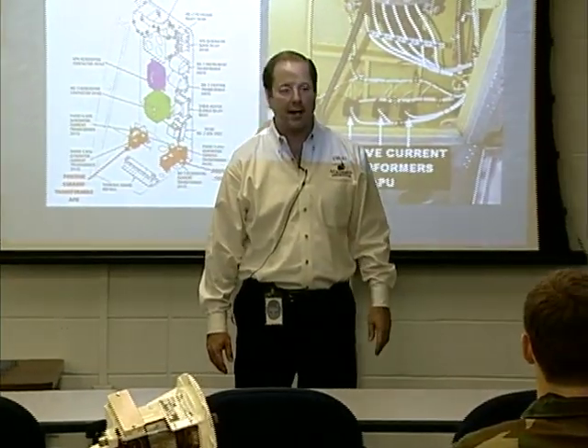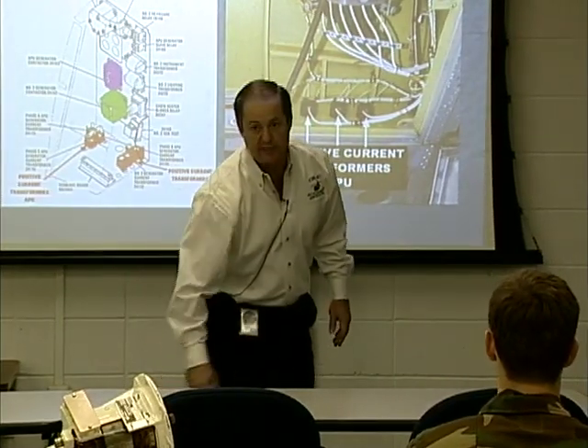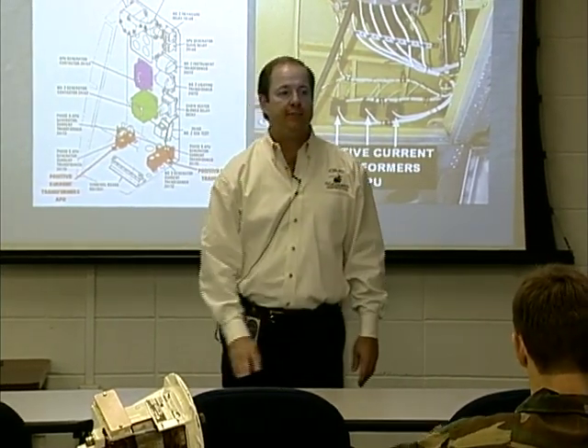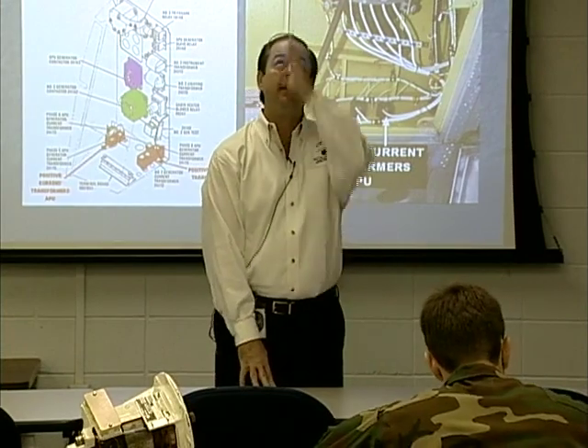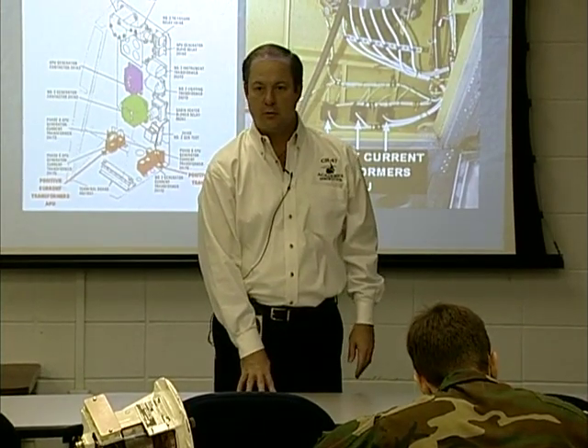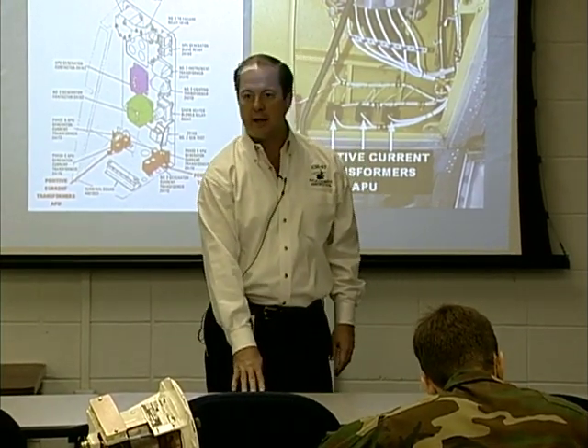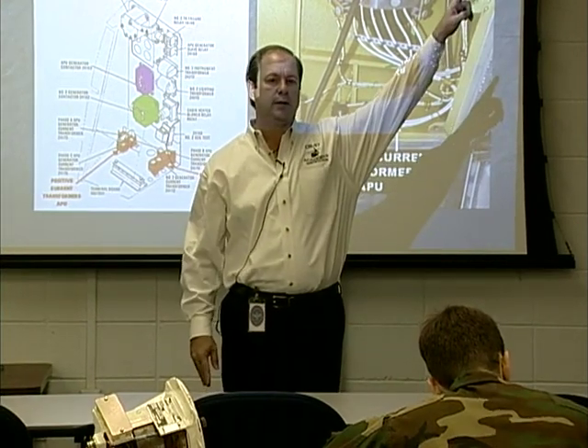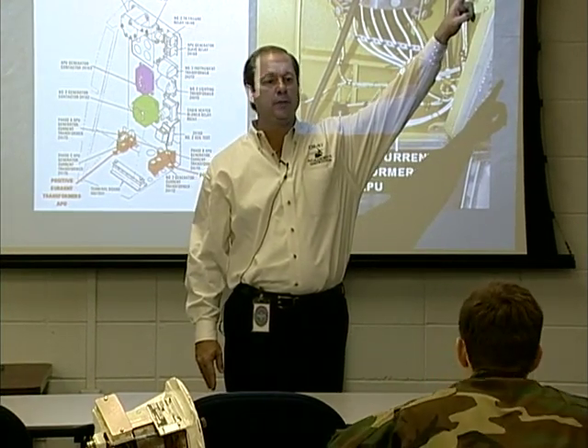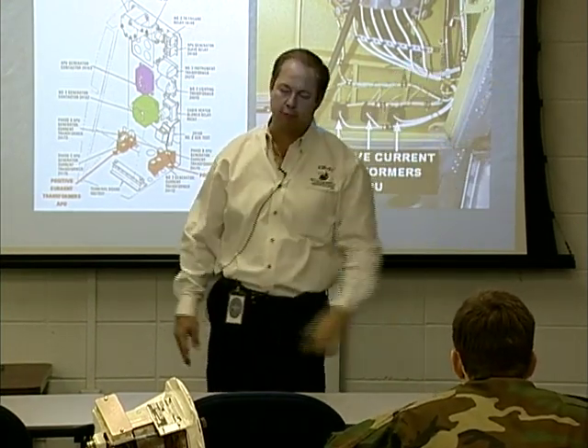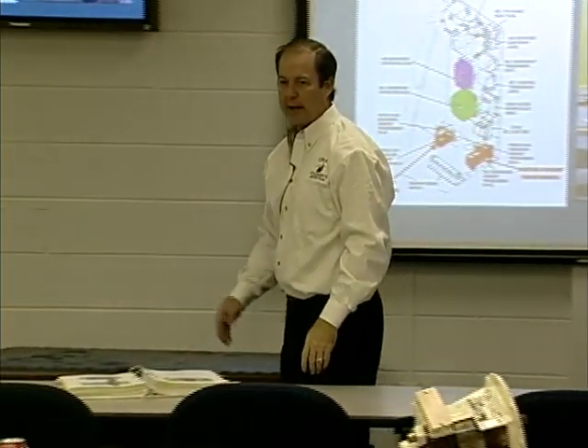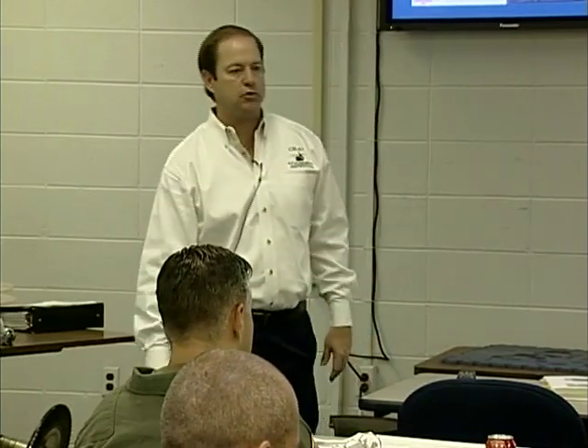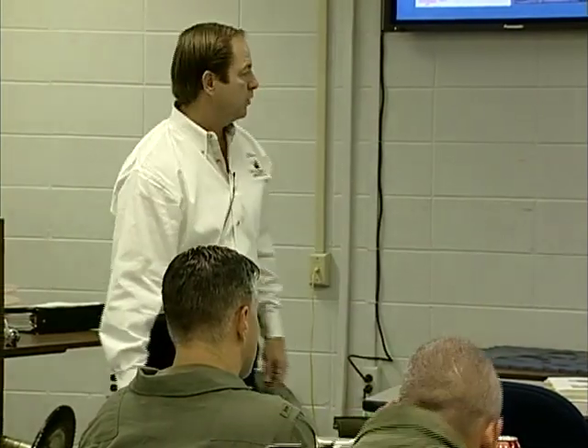Where they are located: if you stand on the tarmac, if this is my ramp down and level, if you butt yourself up against directly underneath the APU, against the ramp, take half a step back, point directly up to your left, you're going to by default be pointing to them. They're often referred to as the donuts, but in reality those are your negative current transformers for the APU generator, which is providing for the same process.